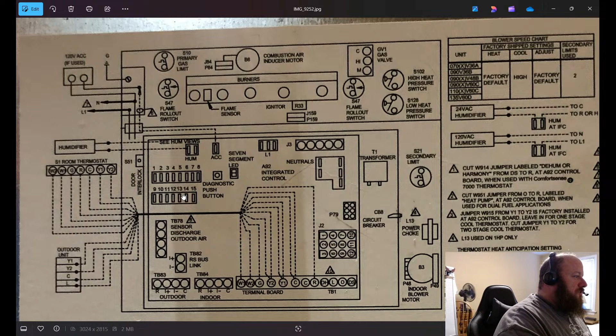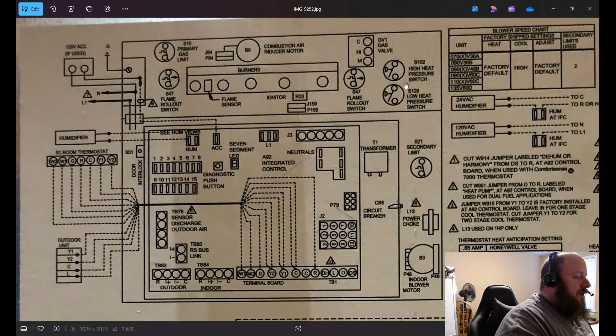You have primary gas limit, you have your temperature switch there, and a flame rollout switch. You have a temperature switch there as well. If you go to your right here, another flame rollout switch, temperature sensor. Then you have a high heat pressure switch and a low heat pressure switch. As you can see, we have, again, pressure switches. It might not be the same pressure switch you use in refrigeration, but it's still the same icon drawn.